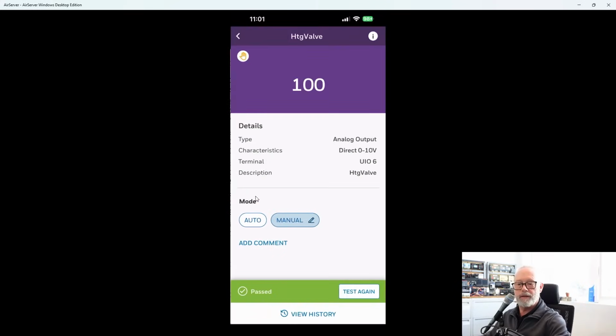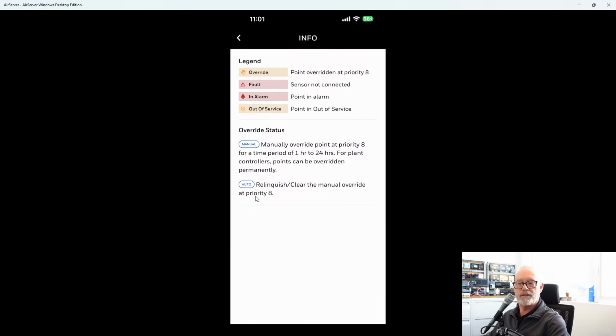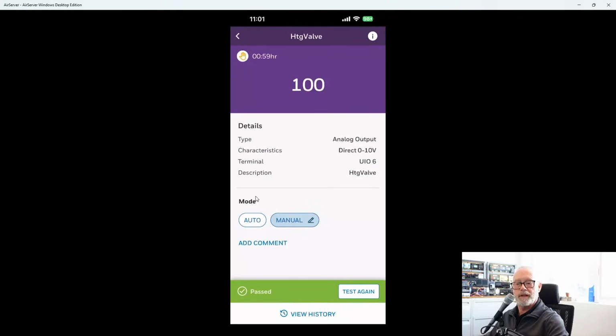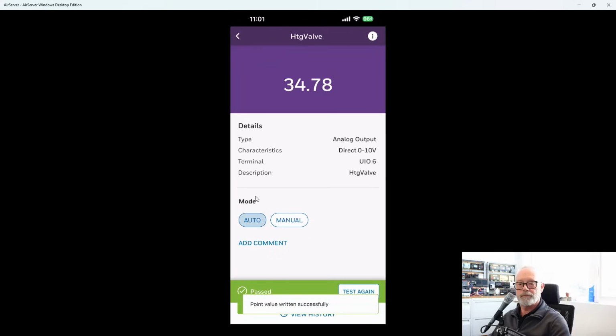I can go back in there. You'll see the hand there saying it's an override. If you're not sure what this display is telling us, we can hit the I button, and it gives us a legend and statuses of what to see on the screens. We can take the point, put it back to auto, and it's off controlling again.